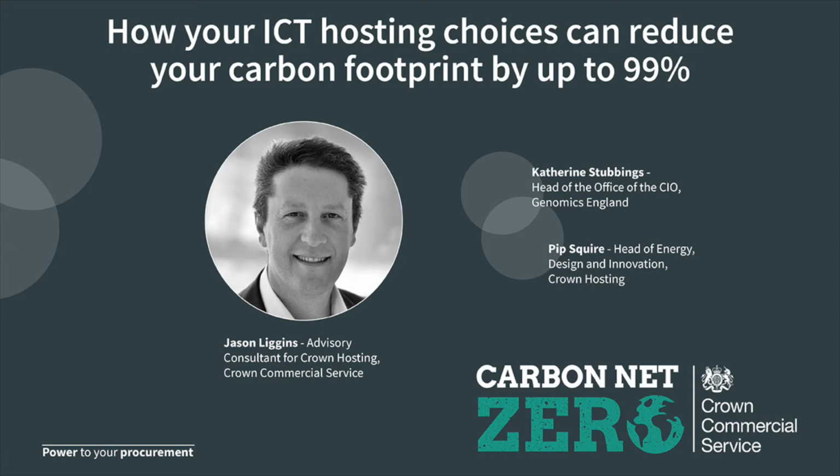And if you do that, you get rid of a whole section of plant, which reduces capital cost as well as economic cost in terms of maintenance and operational cost. So that will have a huge impact on the overhead in terms of how you build it. So as data centers, we're working really hard to reduce the parasitic loads required to support the IT. That's the power that's in the PUE metric. The one question that we can't answer, as it's outside our direct control, is, does the IT actually need all the power it's using directly?